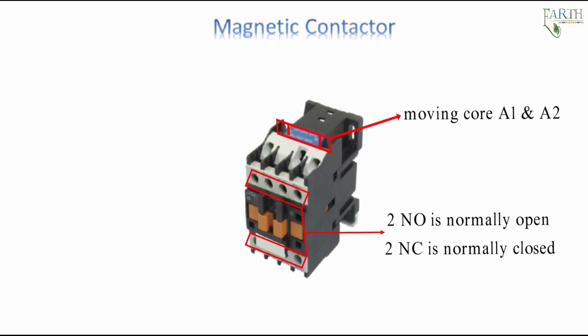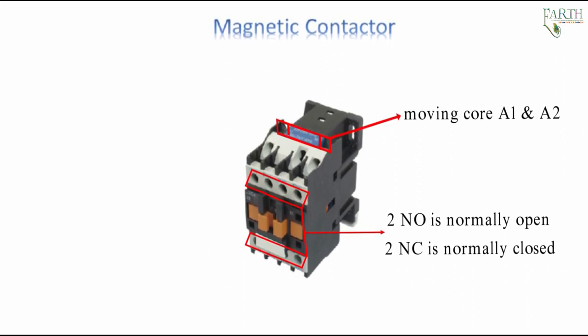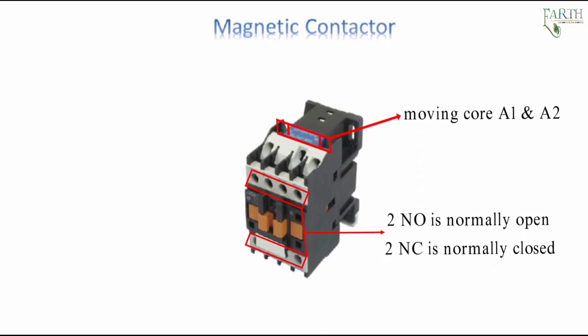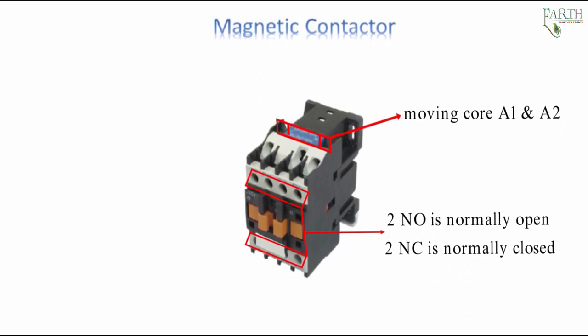When it switches a large amount of electrical power through its contacts, it is designated by the special name 'contactor.' Contactors typically have multiple contacts, and those contacts are usually, but not always, normally open, so that power to the load is shut off when the coil is de-energized.